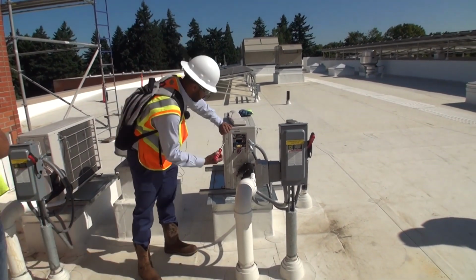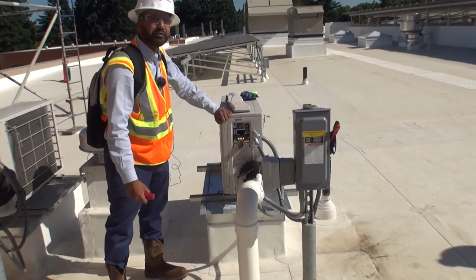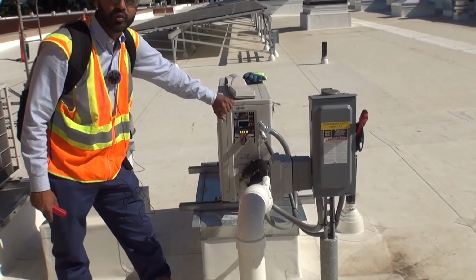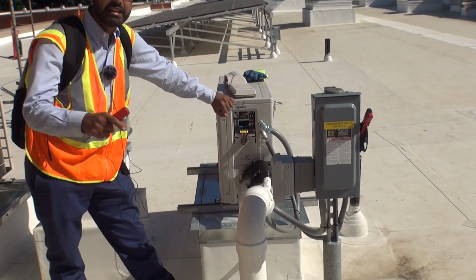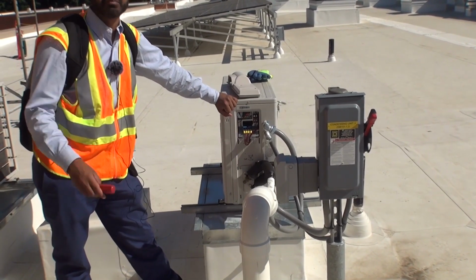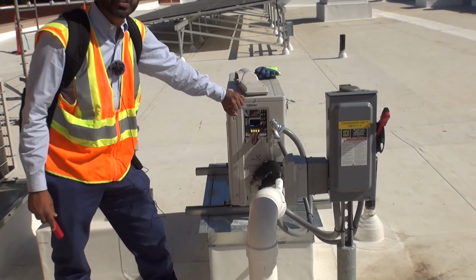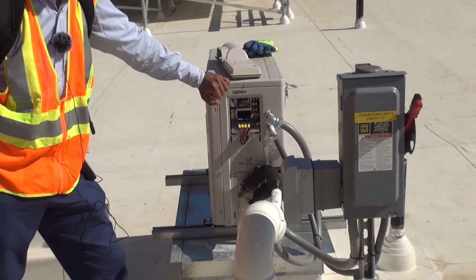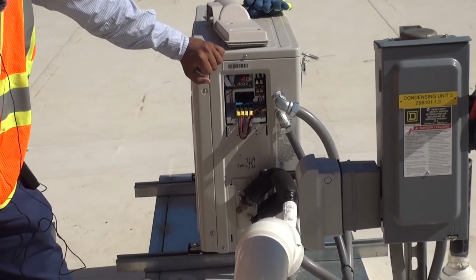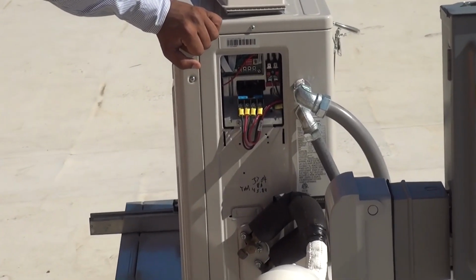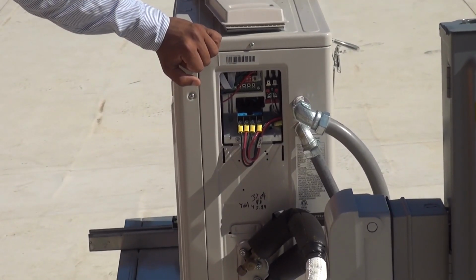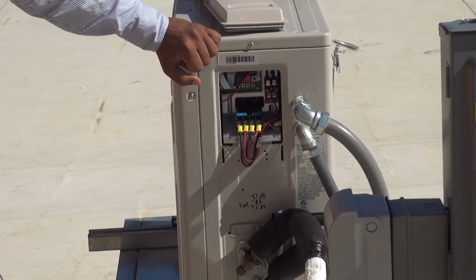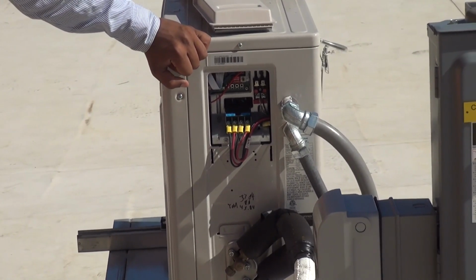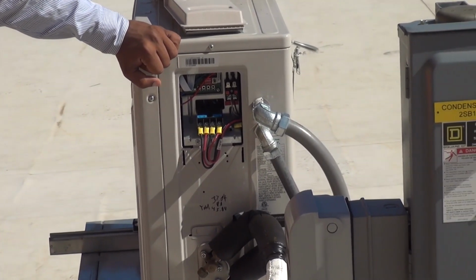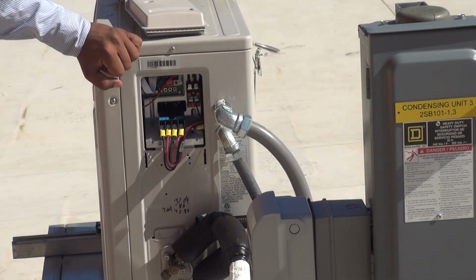One last thing we need to cover is our K buttons over here. We have a set of 4 buttons that control different modes. You can get it into heat mode, test mode, defrost mode. You can force the unit into these modes either for testing purposes or after it's been worked on to make sure it's all good to go. That's part of our whole commissioning process. We stick it into cooling mode, see it run for 15-20 minutes, see if it actually meets temps, and that'll be good to go.